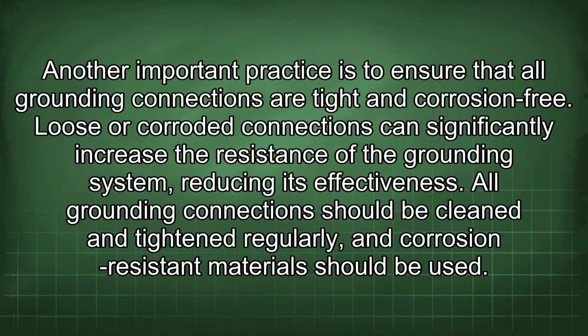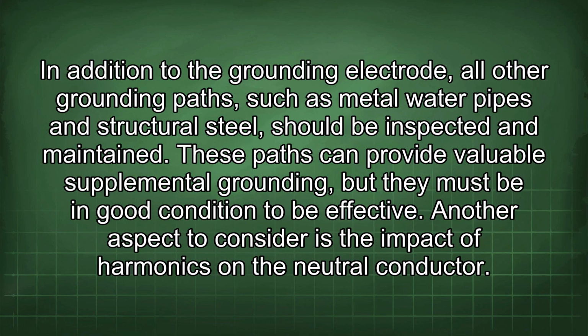Another important practice is to ensure that all grounding connections are tight and corrosion-free. Loose or corroded connections can significantly increase the resistance of the grounding system, reducing its effectiveness. All grounding connections should be cleaned and tightened regularly, and corrosion-resistant material should be used. In addition to the grounding electrode, all other grounding paths, such as metal water pipes and structural steel, should be inspected and maintained. These paths can provide valuable supplemental grounding, but they must be in good condition to be effective.